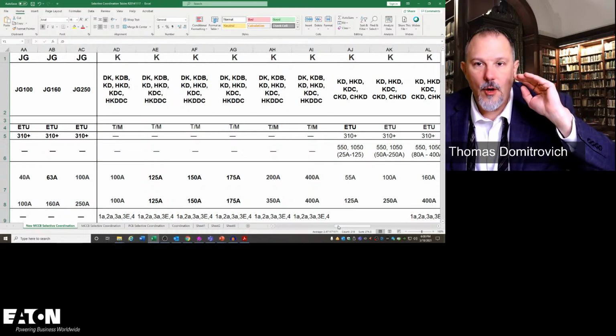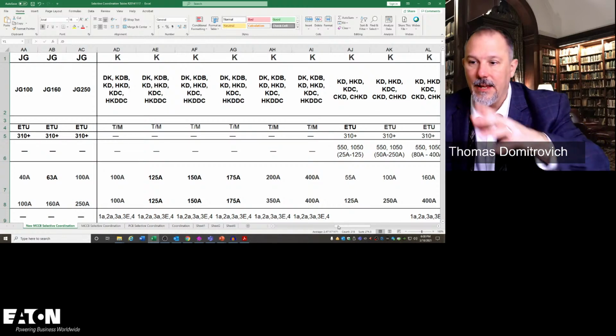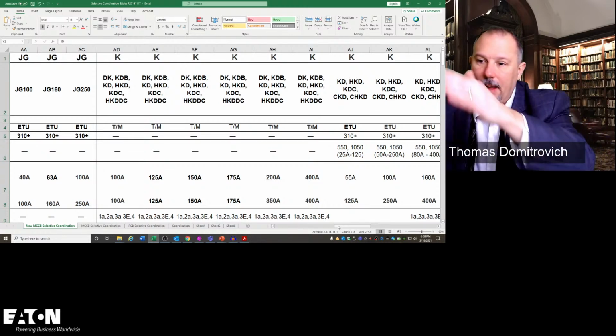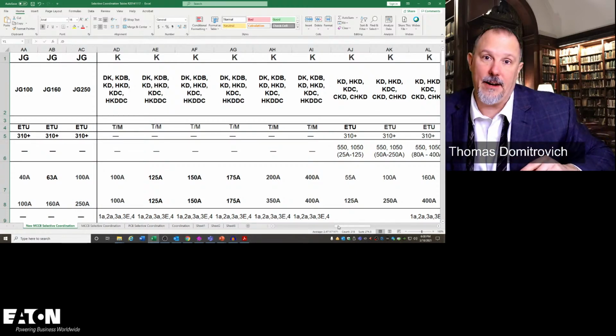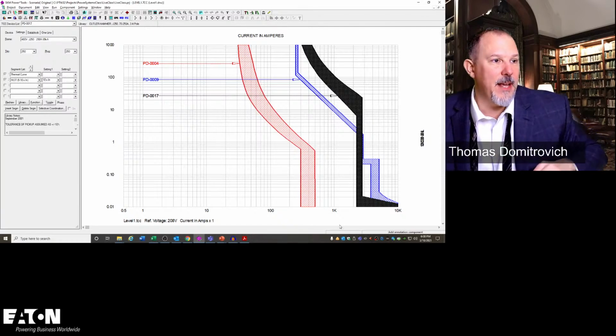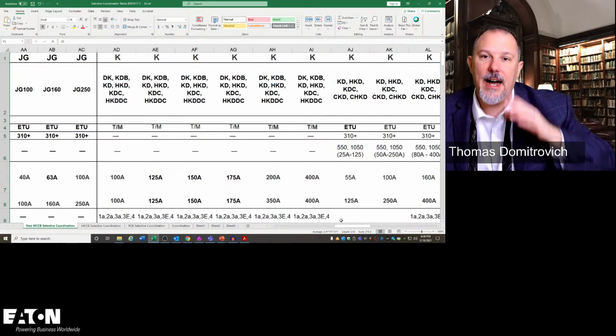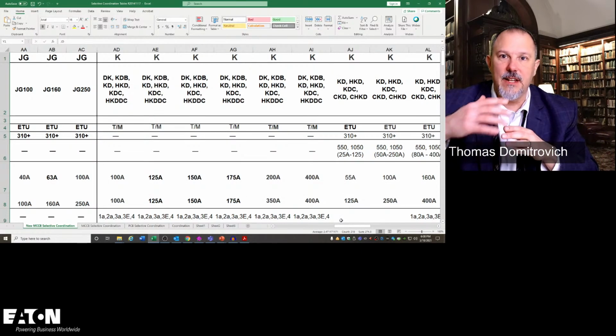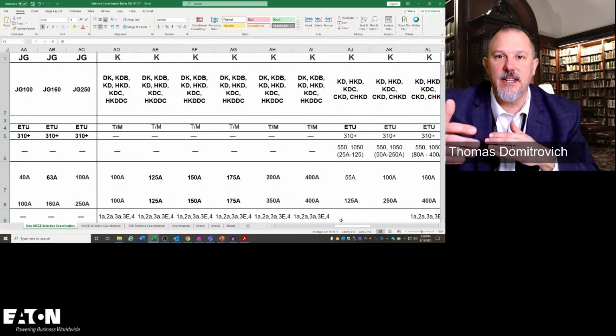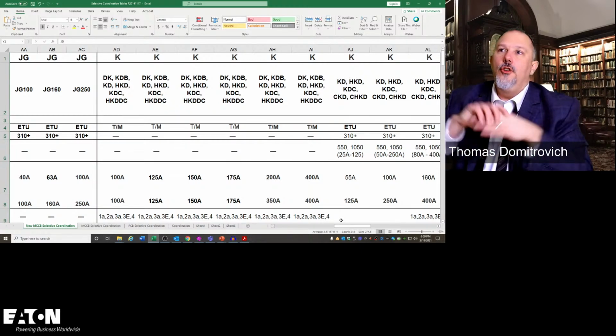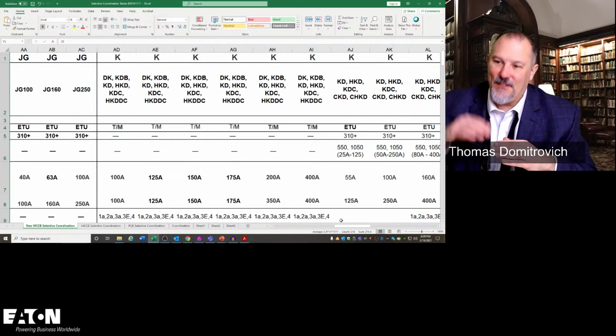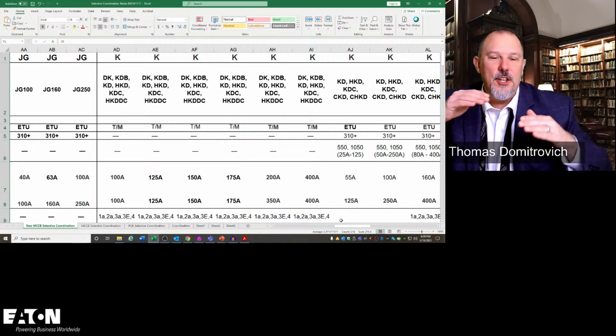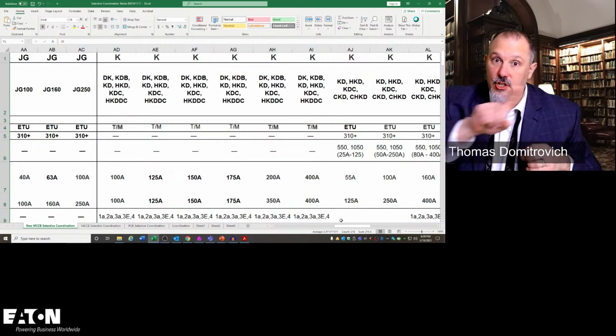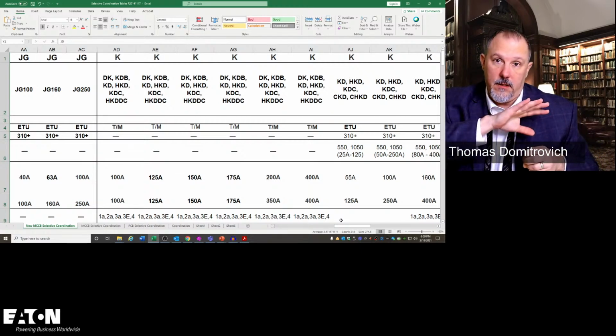If you investigate a little bit further, yeah, arc flash is going to be higher, right? Why is arc flash going to be higher? Because I have put in an intentional delay. Now I've increased the size of the conductor. You could say, well, fuses are your friend. You could say that, and I'll show you what a fuse will do for you, and it'll bail you out of some problems.